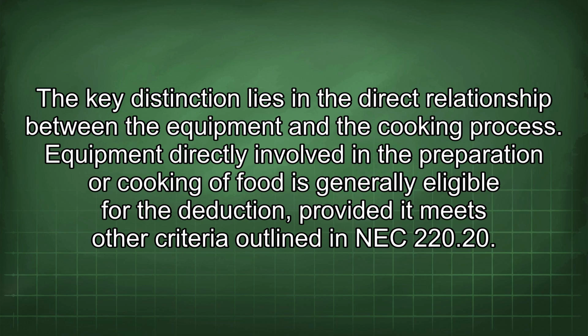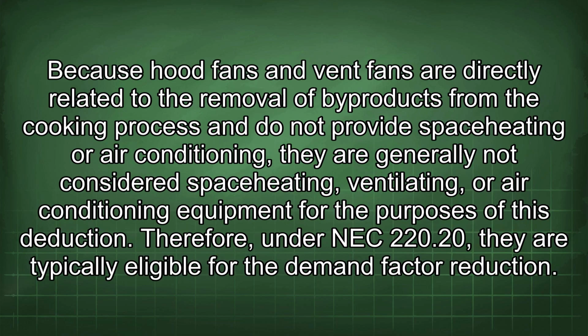Equipment directly involved in the preparation or cooking of food is generally eligible for the deduction, provided it meets other criteria outlined in NEC 220.20. Because hood fans and vent fans are directly related to the removal of byproducts from the cooking process and do not provide space heating or air conditioning, they are generally not considered space heating, ventilating, or air conditioning equipment for the purposes of this deduction. Therefore, under NEC 220.20, they are typically eligible for the demand factor reduction.